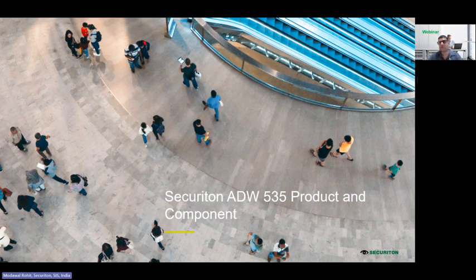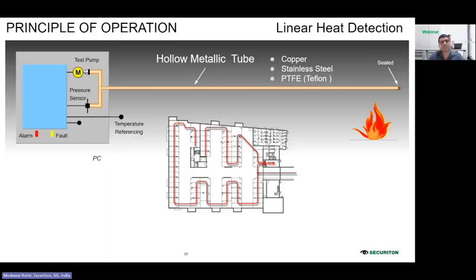The best possible solution, which we are going to discuss, is our ADW535 for this kind of application. We have installed it in many prestigious installations, and it has been running successfully for ages. If you talk about the principle of operation, ADW535, which is the model, is a linear heat detection system based on the air-filled sensing tube principle. It is nothing but pneumatic heat detection. The core principle is that the system uses robust sensing tubes, which can be of metal or plastic. It is installed along ceilings, cable trays, tunnels, conveyors, or machinery, depending on the application where you are using this product.